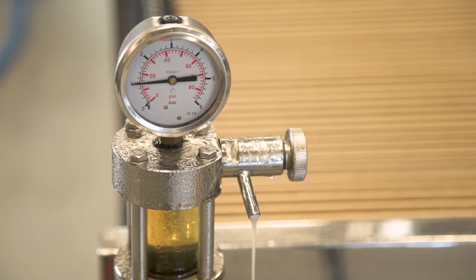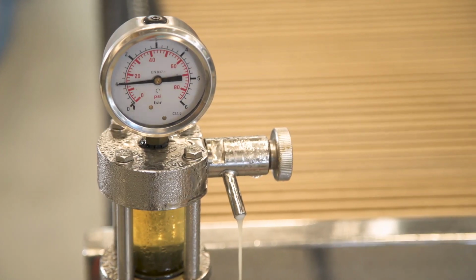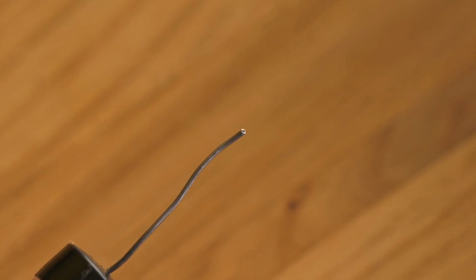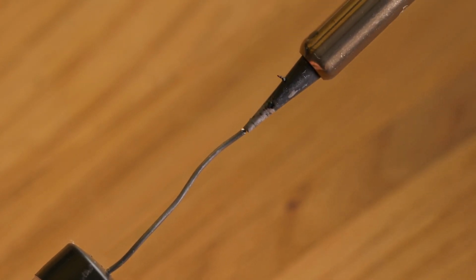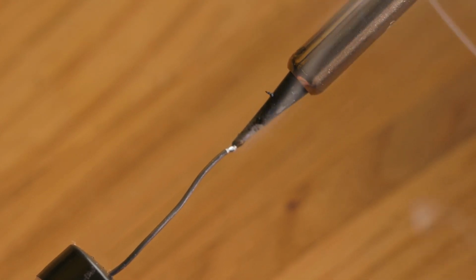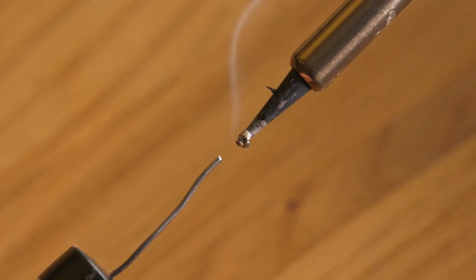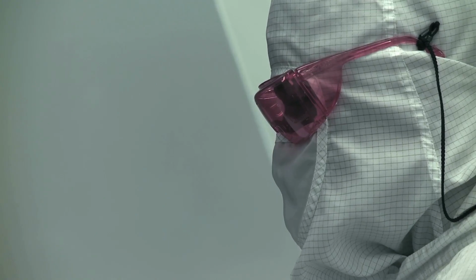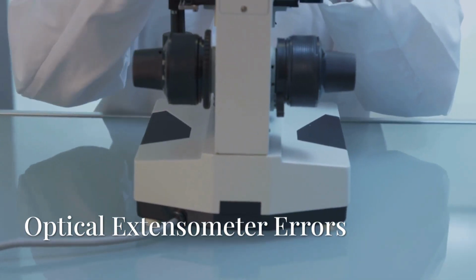Moisture especially can damage the strain gauges used in many models of an extensometer. Short-term condensation normally does not cause permanent damage, but long periods of exposure can degrade the gauges and wires. If an extensometer must be exposed to moisture, it is recommended that the user dry it as soon as possible and store it in a container with desiccant.